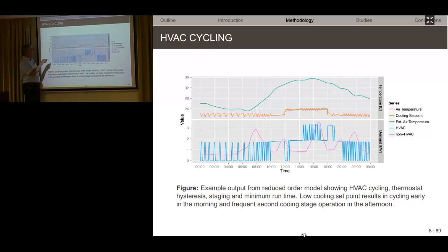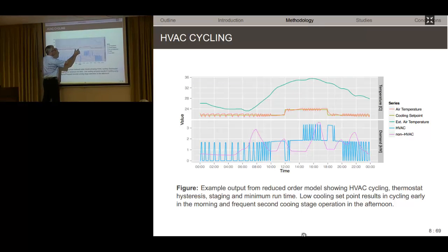This is just to show you the compressor's cycling, right? And you can see long periods of duty cycles, and you can actually see the compressor power turning on and off. And then as it gets hotter, you can see this long period of operation. This compressor stage 1 was running continuously, and then as the set point was raised, what happens? Well, the compressor turns off for a few minutes, 10, 15 minutes, but then comes back on. And it's still getting hotter, and that first stage is not enough, so the second stage has to come on. You see that? Cycling on and off.